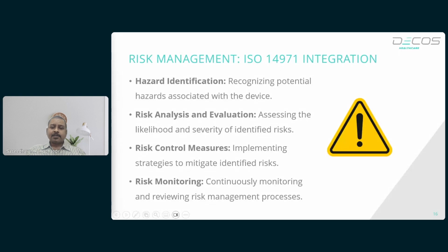Risk management is critical. ISO 14971 is a key standard for medical devices, seamlessly integrating with both US FDA and EU MDR regulatory frameworks. It provides a structured approach to identifying, assessing, and mitigating risk throughout the product lifecycle, ensuring compliance with global safety and performance requirements.